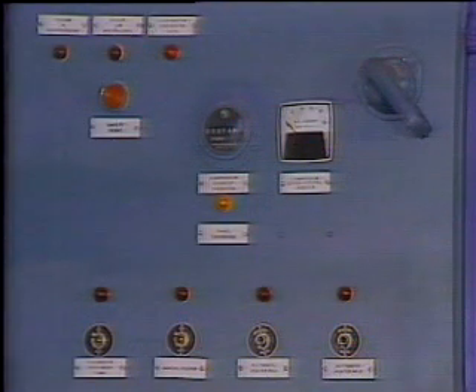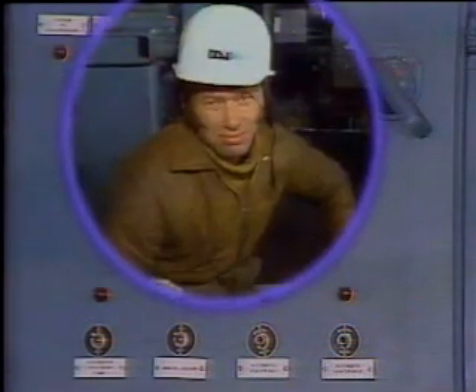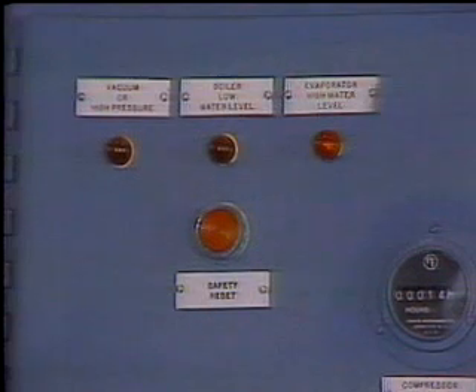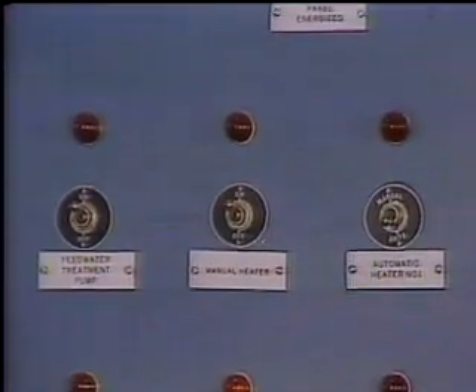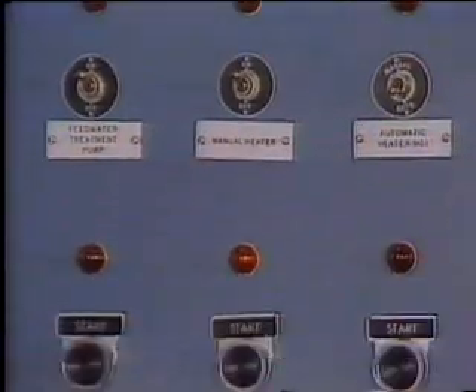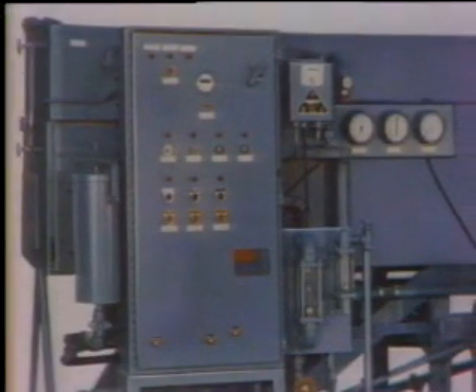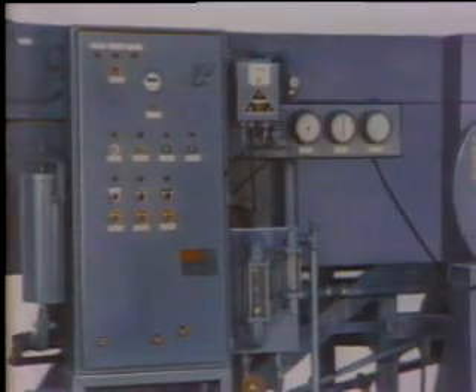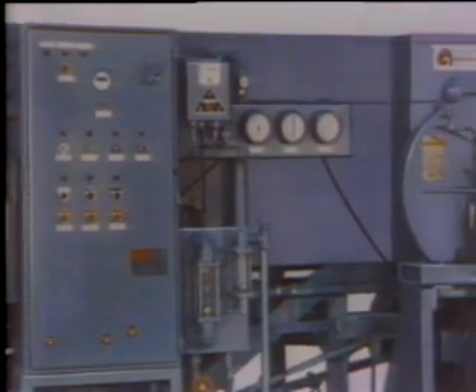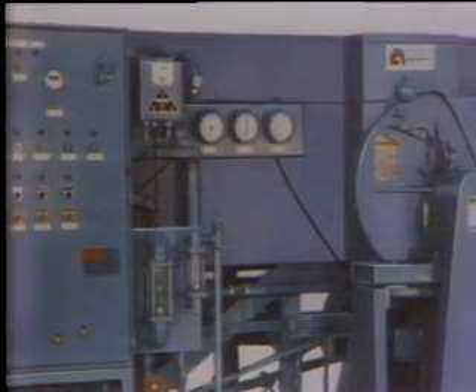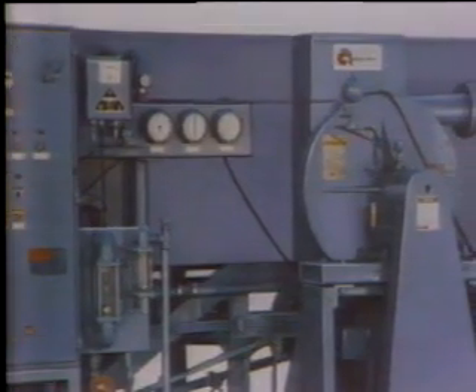Wait a minute now. What's happened here? An automatic shutdown. That's what happened to you, isn't it, Sam? It can occur during the startup procedure for several different reasons. Usually, it'll be due to the recirculation water dropping in temperature. Naturally, this drop in temperature reduces the pressure in the evaporator.